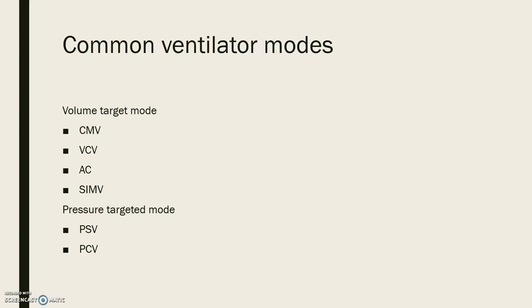Continuous mandatory ventilation, or CMV, is one of the standard modes of ventilation. During pressure-controlled ventilation, two pressure levels are maintained: the lower level of PEEP and the upper pressure level. The resulting tidal volume and decelerating flow are variable and depend on changes in lung mechanics. In pressure-controlled ventilation (PCV), the ventilator determines inspiratory time without the patient's participation.